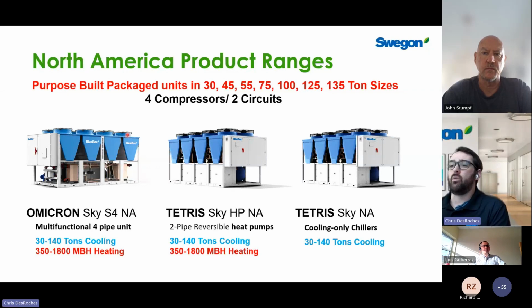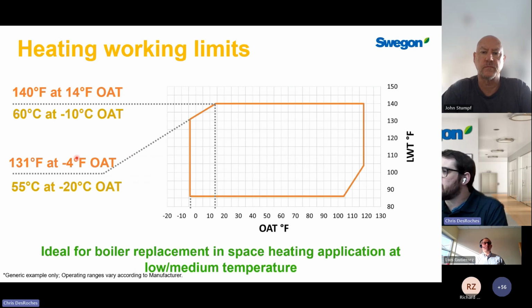So all the machines will have 4 compressors. The larger the machine, the larger the compressors get, and 2 refrigerant circuits. So we often think of 2-circuit chillers or heat pumps as having good redundancy: if an expansion valve's not working or a compressor, we still have the other half of the unit that can work. That is true, but really the benefit we're going to dive into today is defrosting and water temperature control in our building. With a dual circuit heat pump, we're able to coordinate the defrost and have independent defrost. So while half of the unit is defrosting, the other half of the unit is still able to continue providing heating for our buildings.